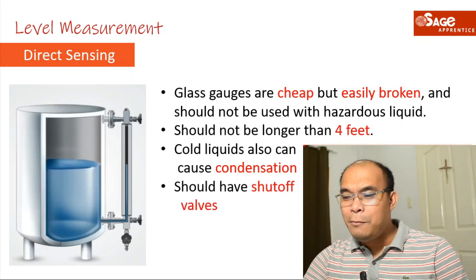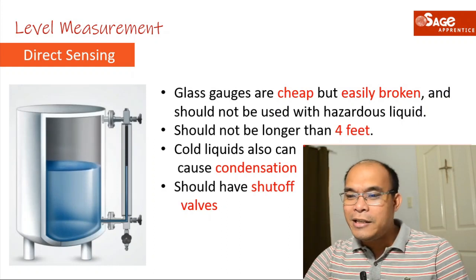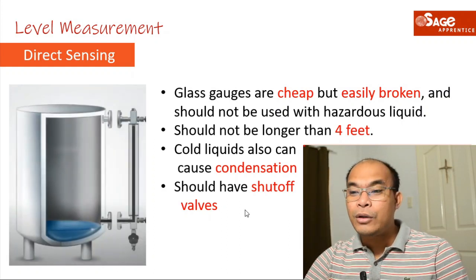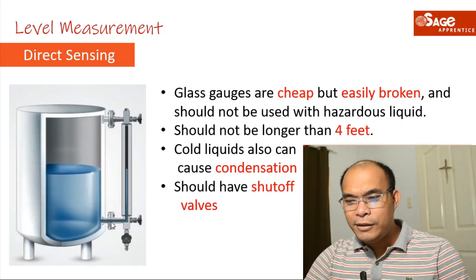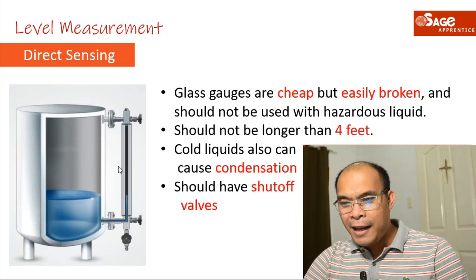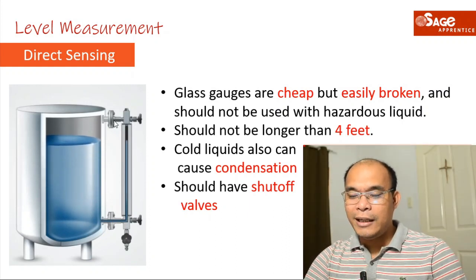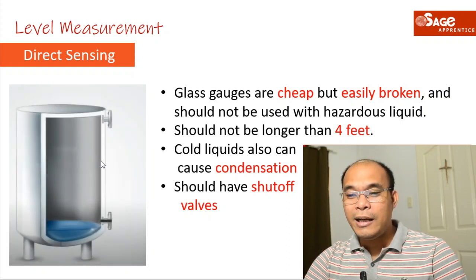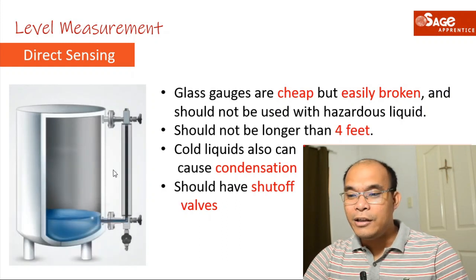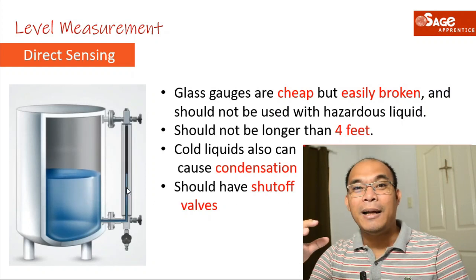The sight glass should also have shut-off valves, located at both ends. For future marine engineers: the shut-off valves are used so that if you need to replace the sight glass, you close the shut-off valve, the liquid can no longer flow through, and then you can safely replace the sight glass. It is very important that the system has shut-off valves.